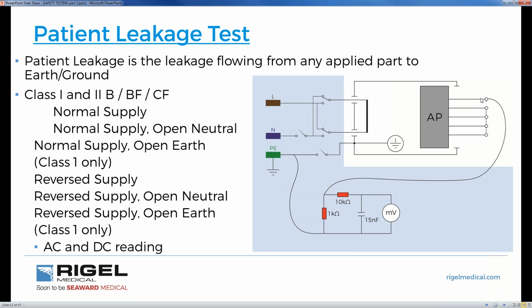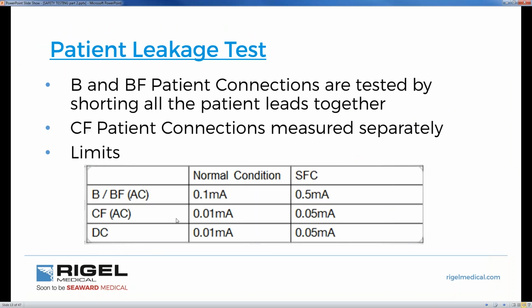Again, this would be in a situation where the patient could be on the hospital bed, and if he is in contact with protective earth, that would be the equivalent leakage that would flow through the patient. Clearly, we don't want, especially for CF, any current flowing. So we have very, very stringent low levels for CF and DC as far as single fault condition is concerned and normal condition. B and BF patient connections are tested by shorting all the patient connectors together, but CF patient connections are measured separately. That's something to bear in mind.